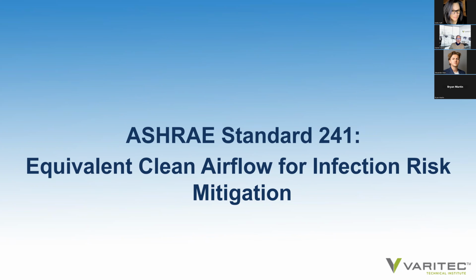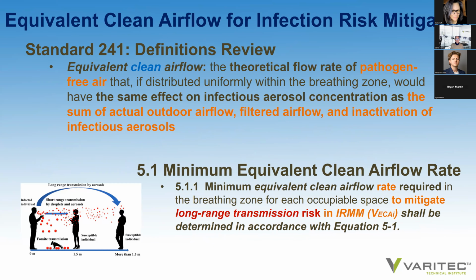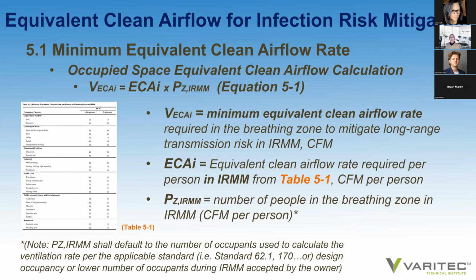So what is equivalent clean airflow? ASHRAE defines equivalent clean airflow, again, in review from the definitions, as the theoretical flow rate of pathogen-free air that has the same effect on infectious aerosol concentration as the sum of actual outdoor air, filtered airflow, and deactivation of infectious aerosols by new technologies such as, well, UV lighting is not that new, but UV lighting, and now apparently ionization is becoming considered as a means of achieving that deactivation of infectious aerosols. So according to the standard, a minimum equivalent clean airflow rate must be achieved at the breathing zone of each occupant to reduce the risk of long-range transmission.